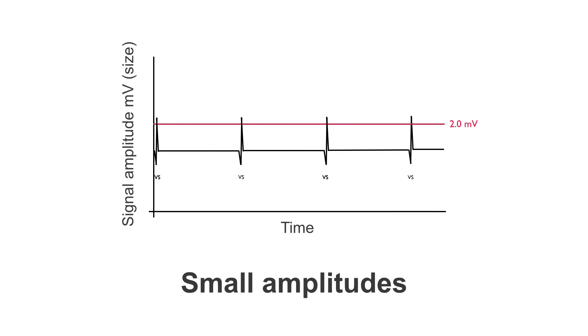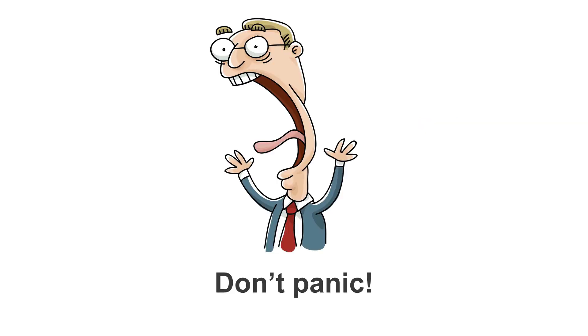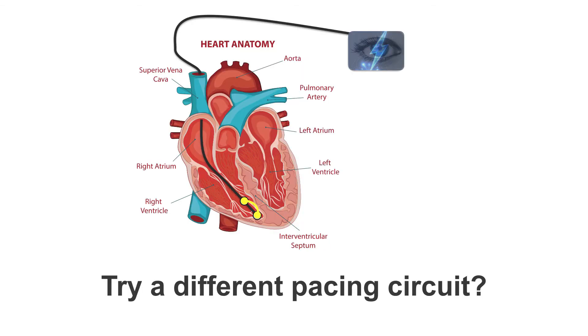So although these are two problems, the important thing to do is not to panic. It does not immediately mean that we have to do something drastic about the device. There are actually programming changes we can make to try and help this. The main one is to try a different pacing circuit.